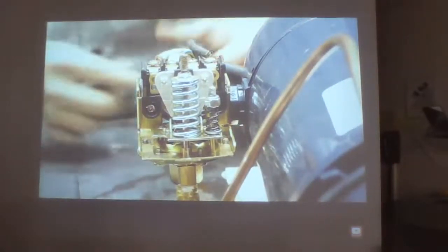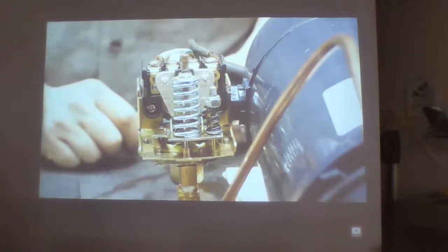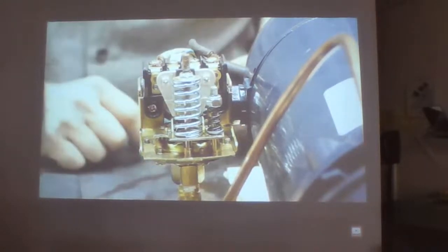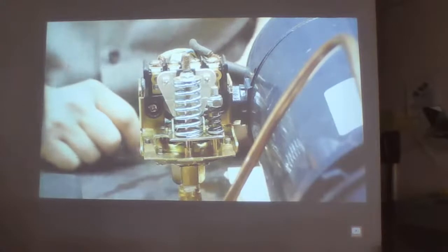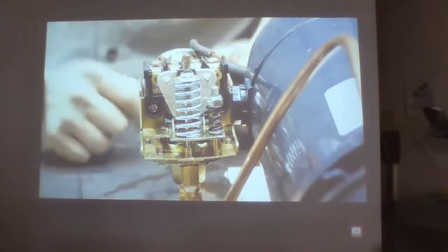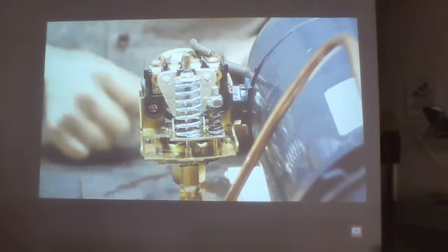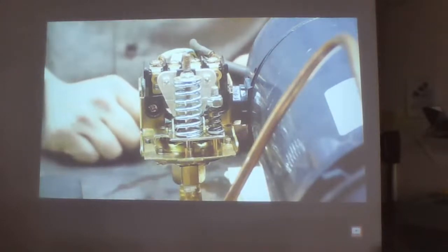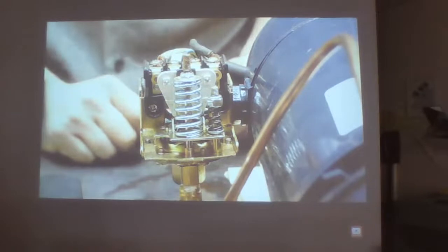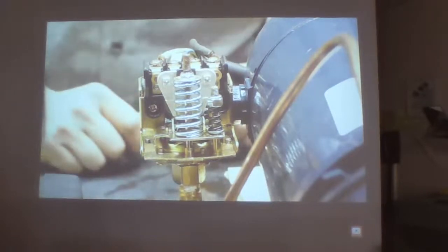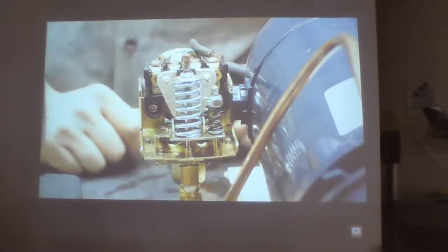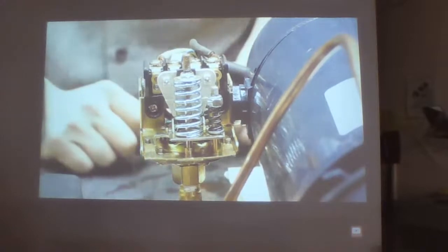If you have a submersible pump, it's most likely going to be set to 40/60 because that's more common with the submersible pumps. And you'll even find some jet pumps, usually smaller horsepower, or some centrifugals more focused on irrigation that run on a 20/40 split. You'll find most pressure switches operate with a 20 PSI or 20 pound differential.